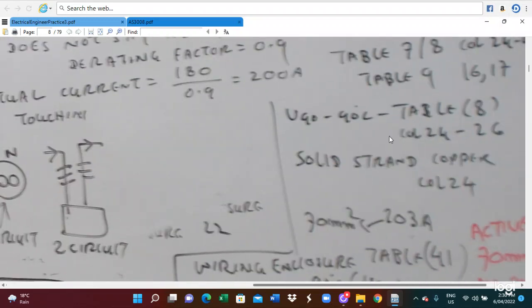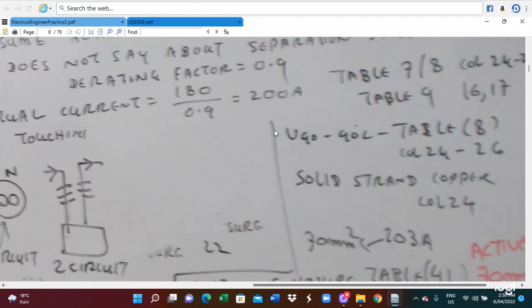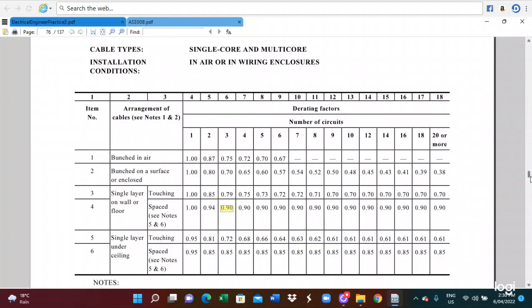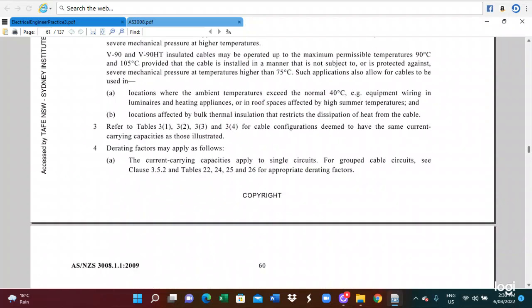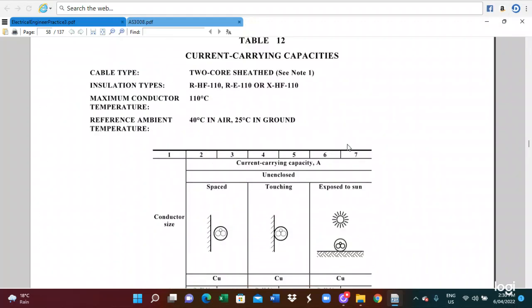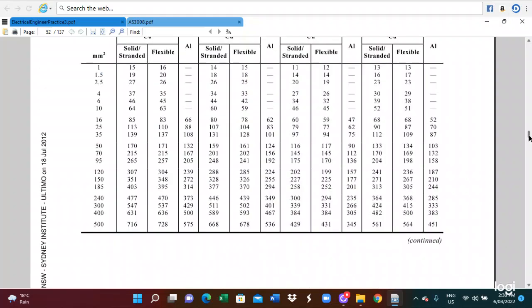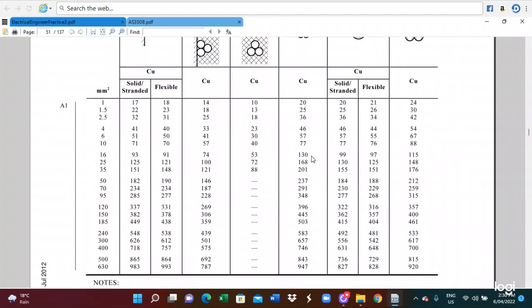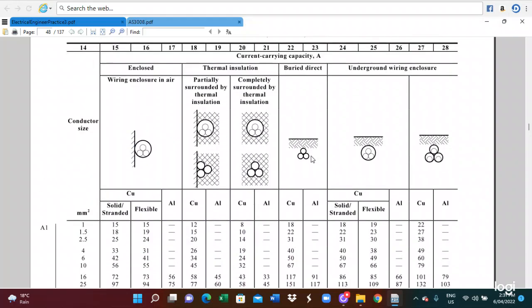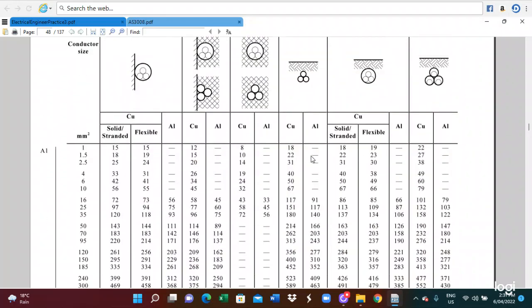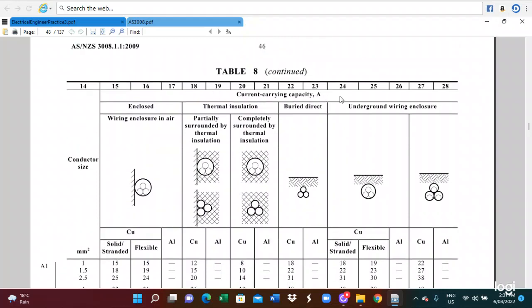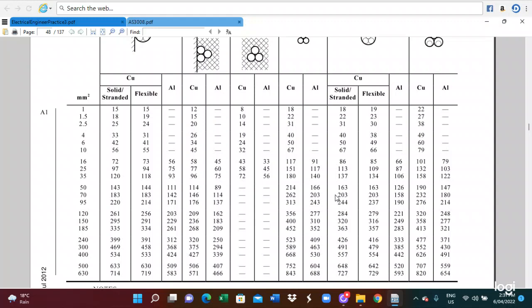Then, based on this 200 ampere, we utilize table 8. So we look at table 8. From here we can see column 24 to 25. For 200 ampere, here is 203, so we get 70 millimeter square. This is the area we calculate: 70 millimeter square.